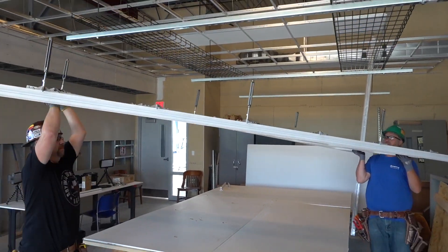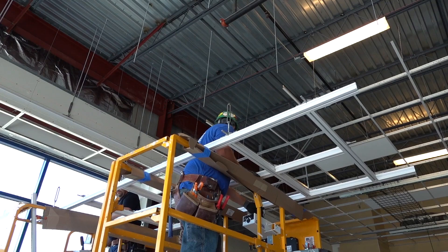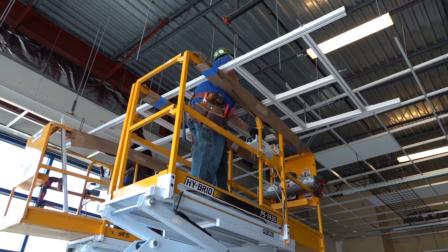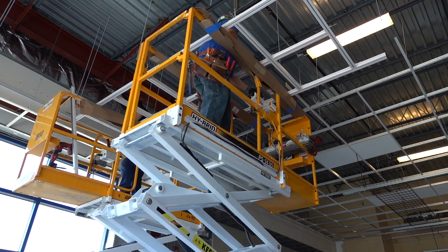The simplest way to install Dynamax is to pre-build on jig tables at your project site, 4 by 12 modules or ladders that you simply lift into place and attach to your 3/8 inch rod drops from structure via the Dynamax turnbuckle.